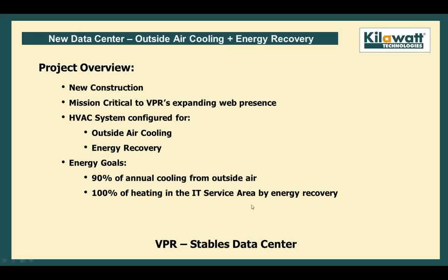Specifically, the traditional design of a data center uses low volume air at a low temperature to remove heat from the computer racks. What we are utilizing, based on a number of articles in the literature, is a very high volume air movement system. By pushing tremendous amounts of air across the computer racks, you can achieve the cooling necessary without a significant temperature delta between what your zone temperature requires and what the air moving across it is.